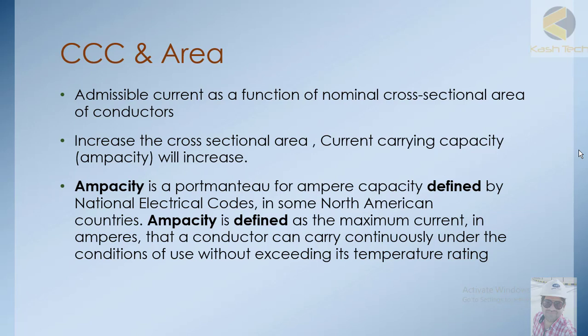Ampacity is defined by the National Electric Code in some North American countries. Ampacity is defined as the maximum current in amperes that a conductor can carry continuously under conditions of use without exceeding its temperature rating.